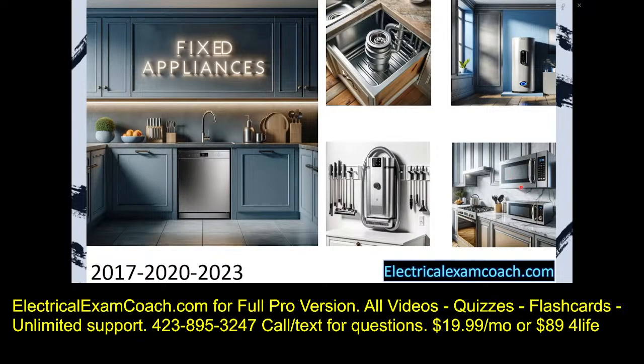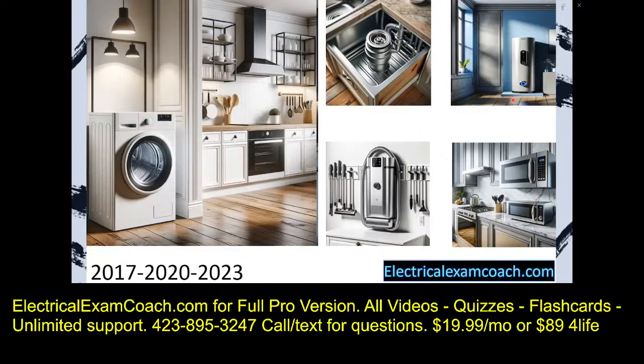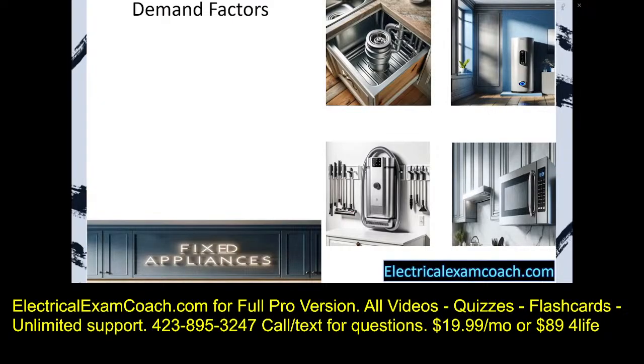And when you fix it to the wall or fix it so it can't move, either with plumbing or mechanical vents or anything else, it now becomes a fixed appliance, and there's a special way that they calculate them when doing a whole home load calculation. What it does not include is dryers or ranges. We're actually going to deal with those separately. So this includes all other fixed appliances except for dryers and ranges. Let's get to it.